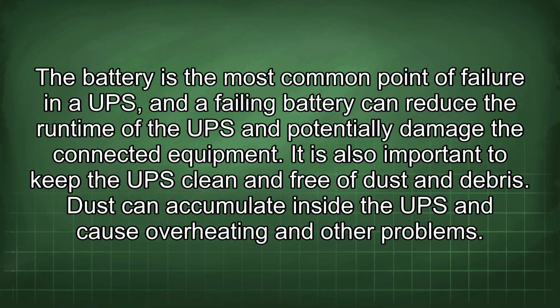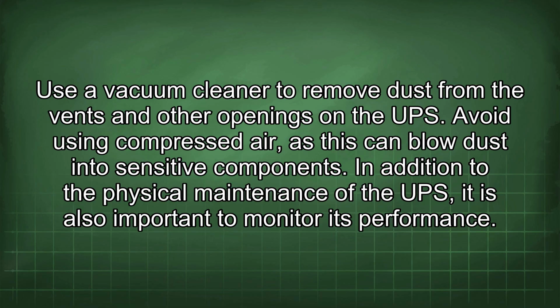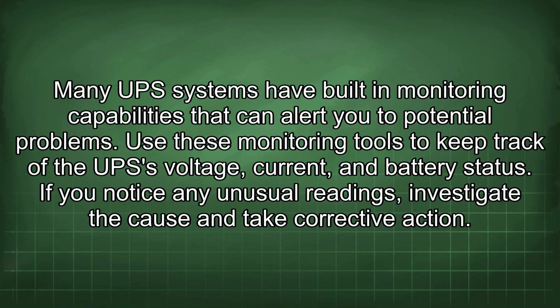Dust can accumulate inside the UPS and cause overheating and other problems. Use a vacuum cleaner to remove dust from the vents and other openings in the UPS. Avoid using compressed air, as this can blow dust into sensitive components. In addition to the physical maintenance of the UPS, it is also important to monitor its performance. Many UPS systems have built-in monitoring capabilities that can alert you to potential problems. Use these monitoring tools to keep track of the UPS voltage, current, and battery status. If you notice any unusual readings, investigate the cause and take corrective action.